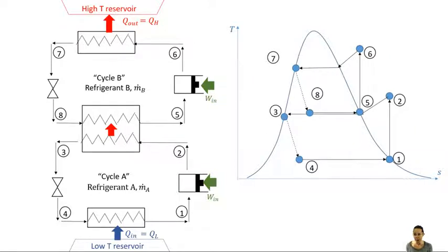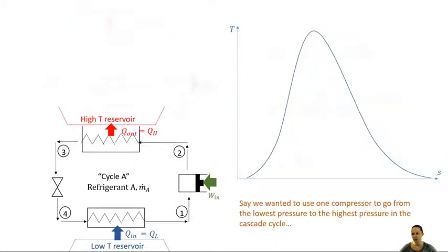and you don't want any air coming into your system. And you can make a similar case for the very top heat exchanger, the condenser. You don't want the saturation pressure at whatever temperature you need to be at in the condenser to be too high, because that increases the cost of your material. So by choosing two different refrigerants, you can tweak the pressure in your condenser and your evaporator to reasonable pressures. All right.